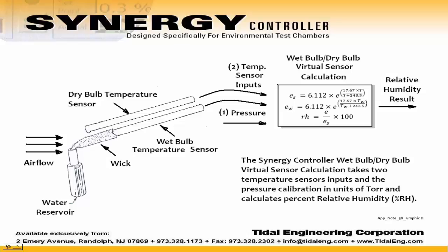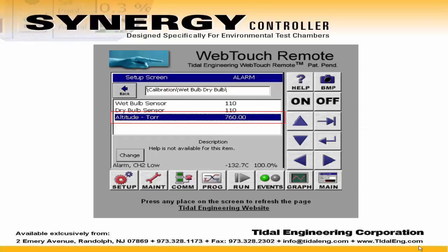To provide the greatest accuracy, the Synergy controller's wet bulb sensor requires moderate airflow. Airflow of 700 feet per minute will provide good accuracy. In addition, the temperature sensor should be shielded from radiant heat. Errors up to 15% can occur if the air movement is too slow or if there is too much heat radiation. The Synergy controller provides a pressure or torr calibration field to compensate for ambient pressure at the measurement site. This improves the accuracy of measurement.